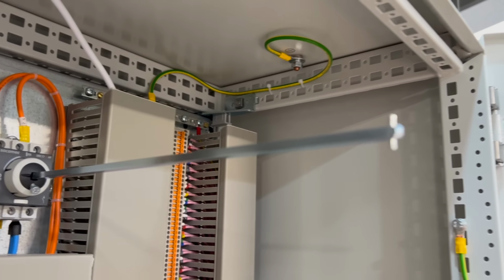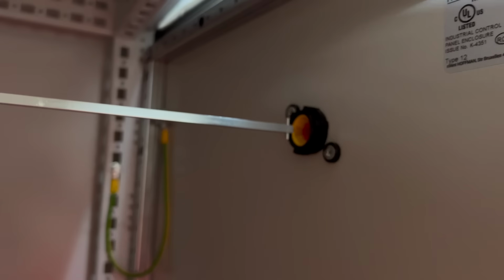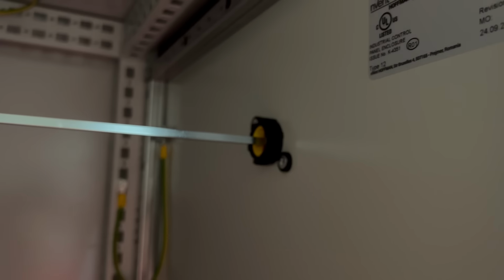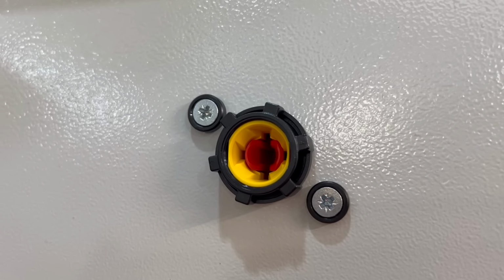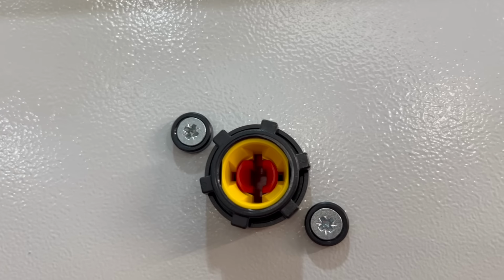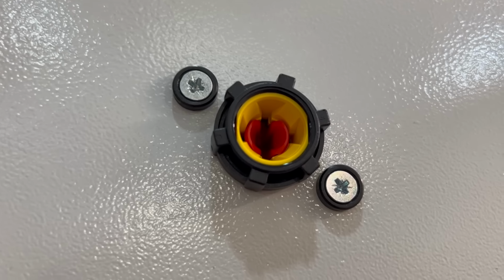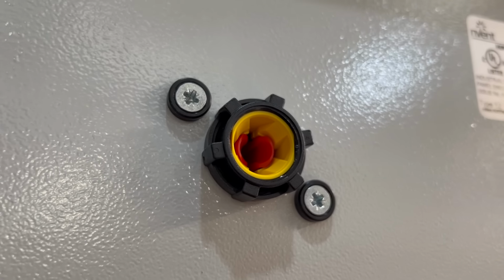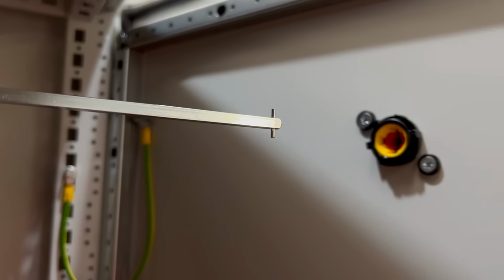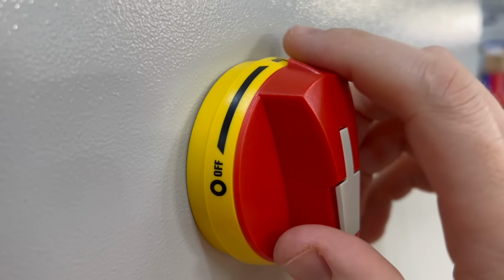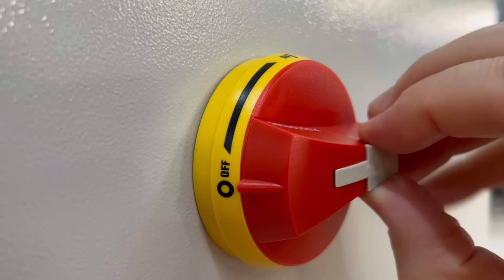It will then have a long bar that extends to the door of the panel and slots into the isolating handle on the front. The back of the door element of the device is often shaped in such a way that the bar is funneled into the operating handle, as it may have a tendency to drop down a bit. And the arc of the door caused by the hinge means it doesn't exactly line up when opening and closing the front.